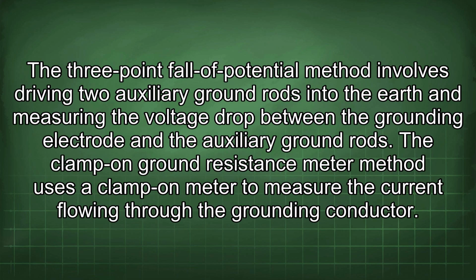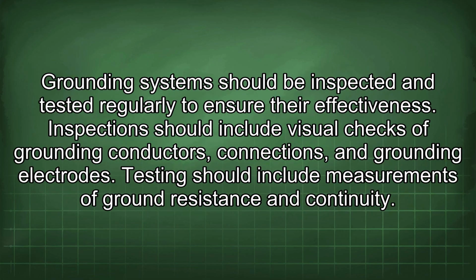The 3-point fall of potential method involves driving 2 auxiliary ground rods into the earth and measuring the voltage drop between the grounding electrode and the auxiliary ground rods. The clamp-on ground resistance meter method uses a clamp-on meter to measure the current flowing through the grounding conductor. Grounding systems should be inspected and tested regularly to ensure their effectiveness.